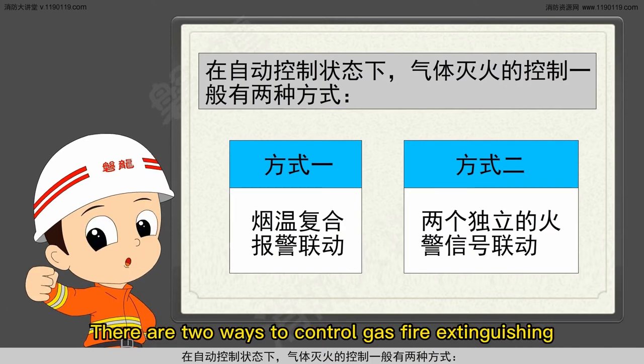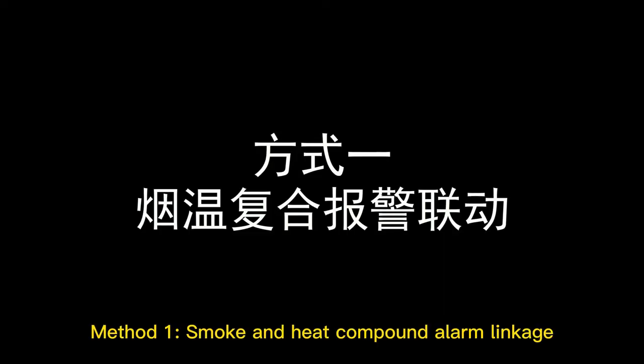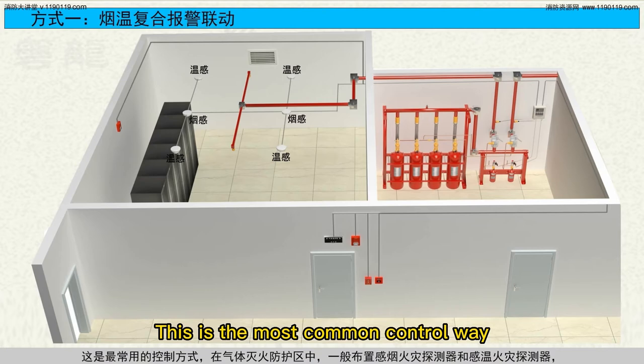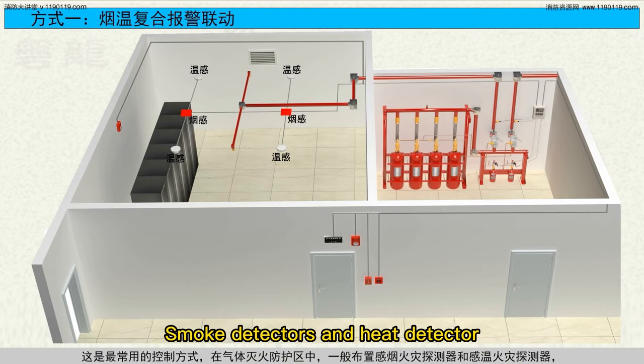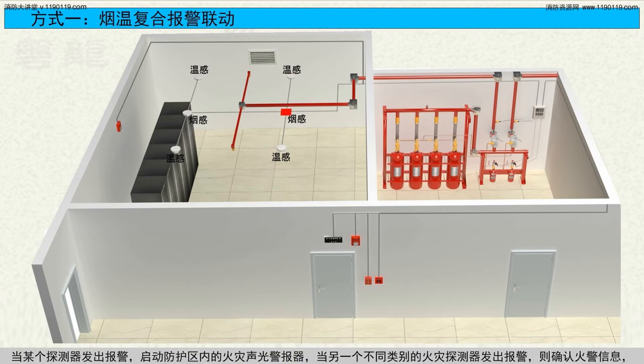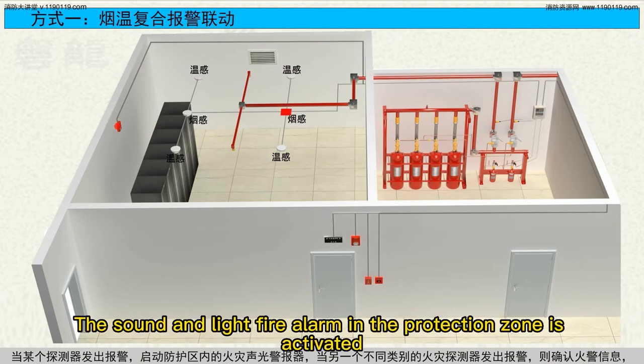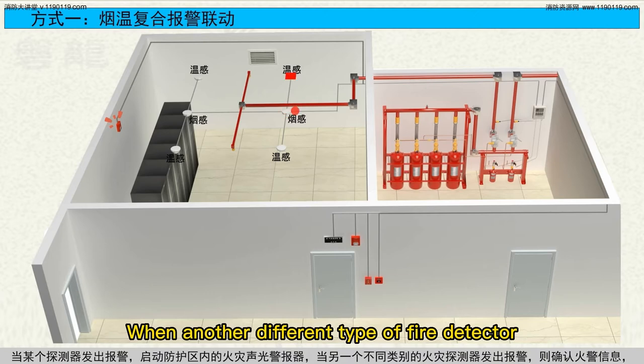Under automatic control status, there are two ways to control gas fire extinguishing: smoke and heat compound alarm linkage. This is the most common control way in the gas fire protection zone. Smoke detectors and heat detectors are generally used. When a detector triggers an alarm, the sound and light fire alarm in the protection zone is activated.